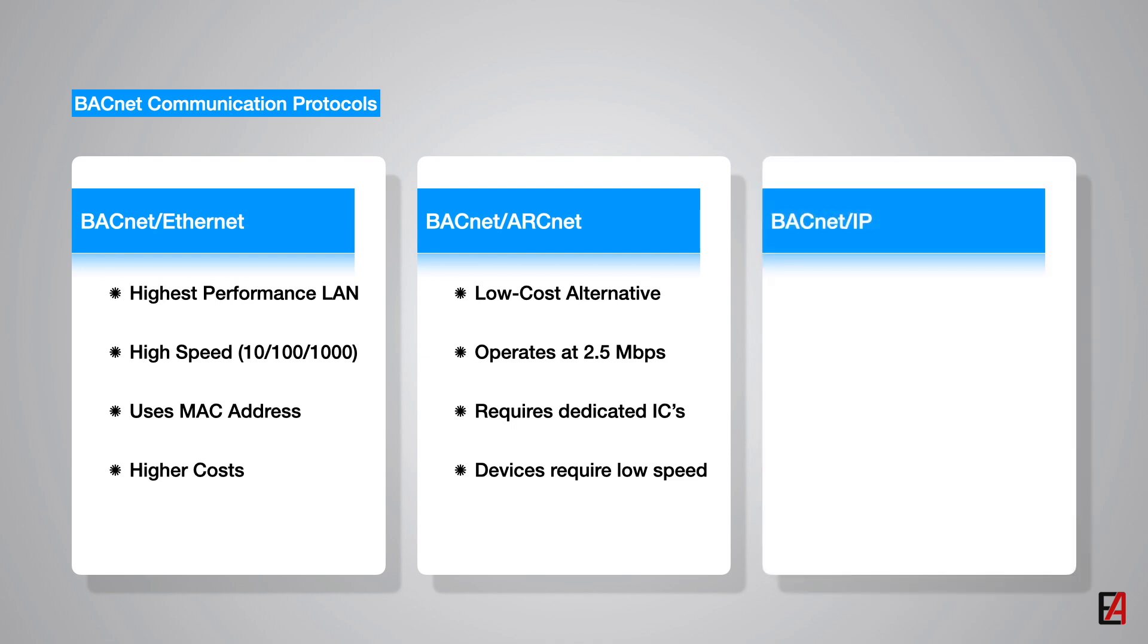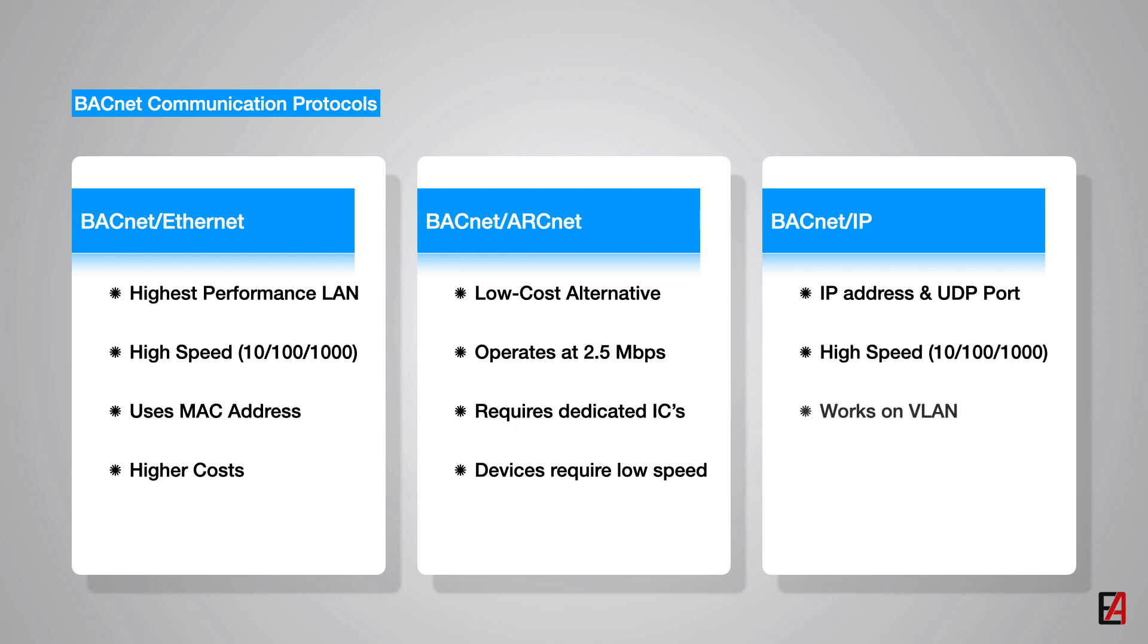The third LAN network is the BACnet IP. The BACnet IP protocol uses IP address and UDP ports for communication with the existing Ethernet network. Also BACnet IP protocol can be used in virtual LAN networks. It supports hundreds of devices and this is the preferred communication protocol of BACnet.